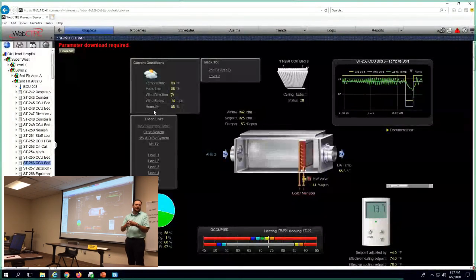And I'll have somebody go through. Every room in the whole building is different. Patient rooms, we want them to have as much control as they possibly can. And we want a quick response, which we went through on the preliminary front ends. We don't want the fan to slow down to try to warm the room up. We want the hot water valve to open when they call for heat. Yep, agree. That's the way it should be.